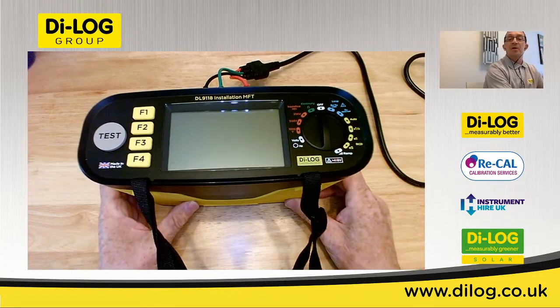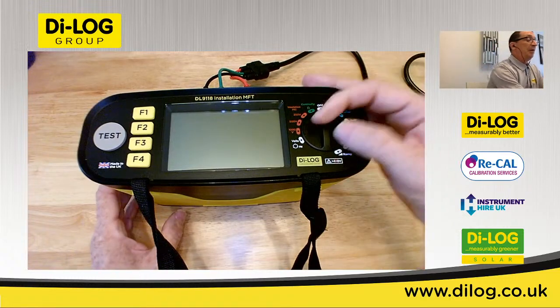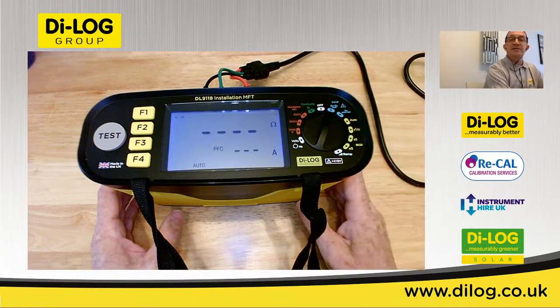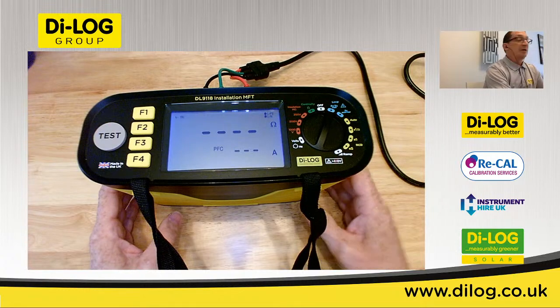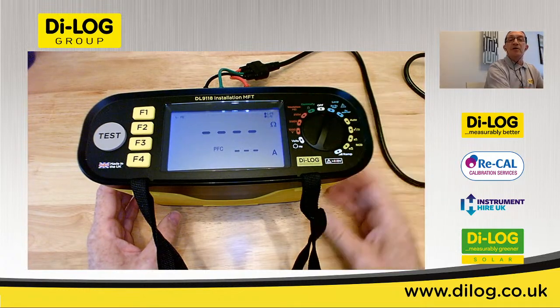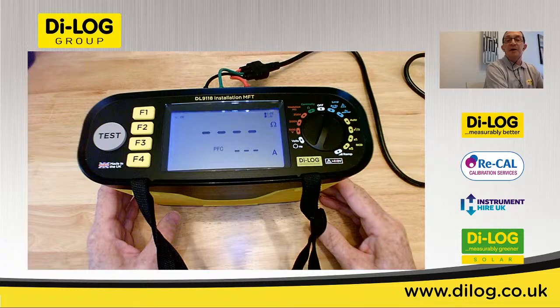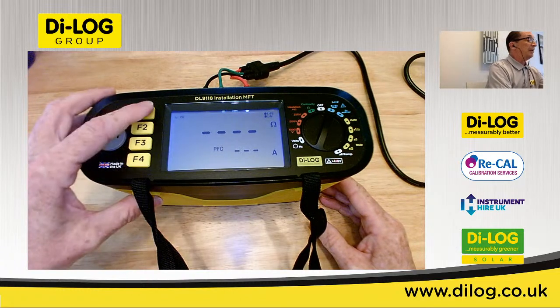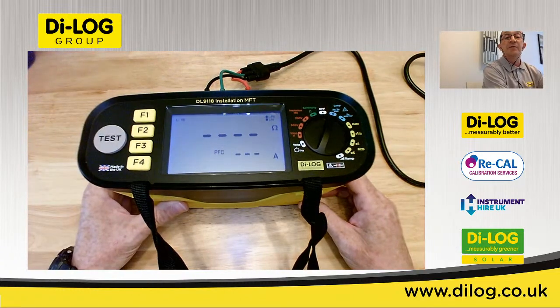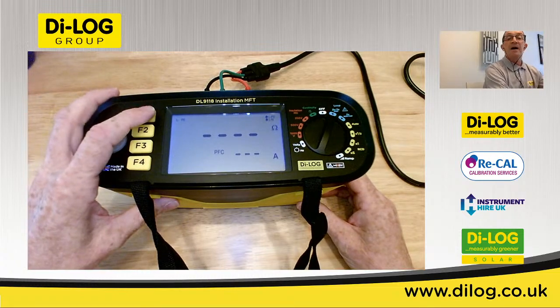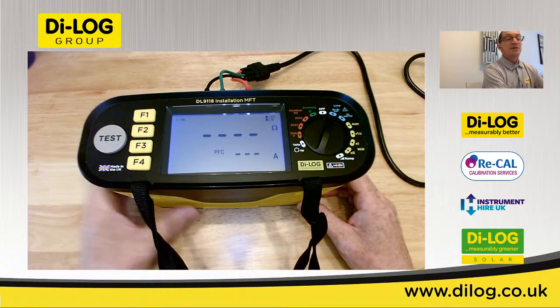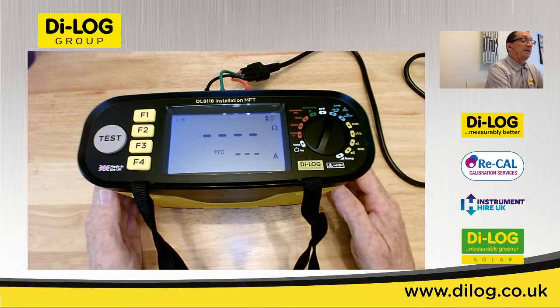Moving on the right hand side of the off position we have our loop impedance tests, and we indicated in the corner that we've got live power going to the unit, and in the top left hopefully you can see that we've got live to earth, and we can toggle across to live and neutral. This is the full current ZE, ZS high current test.